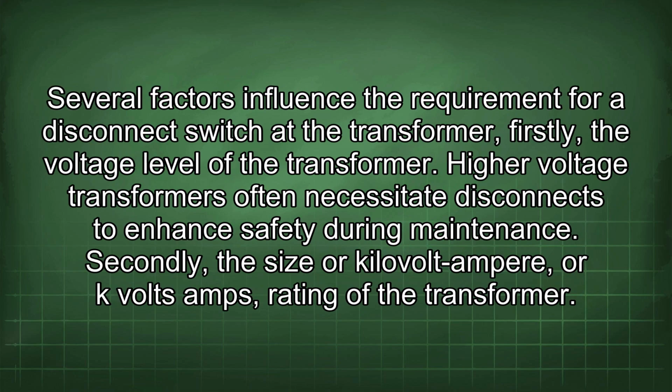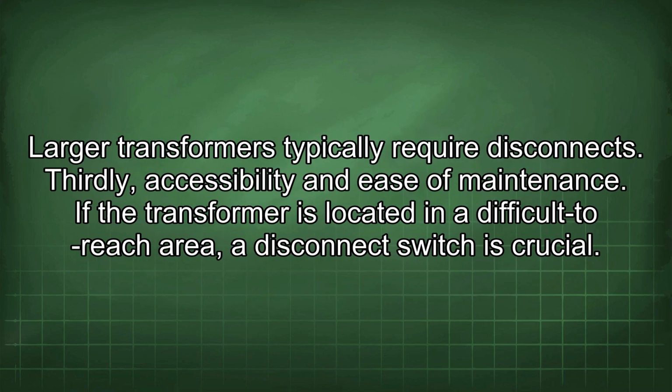Several factors influence the requirement for a disconnect switch at the transformer. Firstly, the voltage level of the transformer. Higher voltage transformers often necessitate disconnects to enhance safety during maintenance. Secondly, the size, or kilovolt-ampere (kVA) rating, of the transformer. Larger transformers typically require disconnects. Thirdly, accessibility and ease of maintenance. If the transformer is located in a difficult-to-reach area, a disconnect switch is crucial.